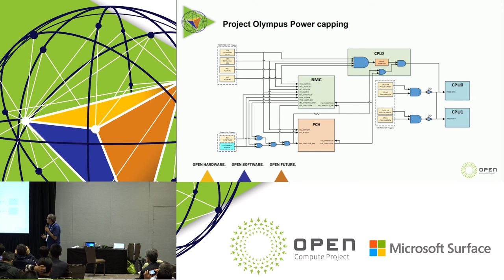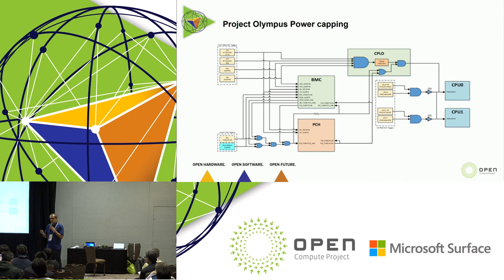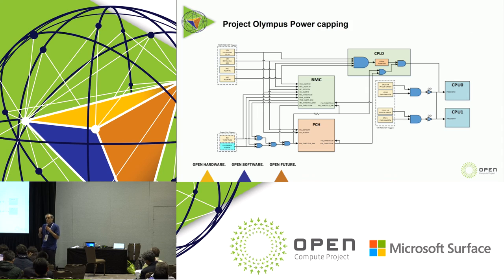The second mechanism is through the interaction between the BMC and Intel Node Manager. When we throttle the CPU, maybe we don't want to stay at the lowest frequency because of the performance impact. But we want to make sure we react to the power event quickly. So we do it through the fast proc hot first, and then the BMC sends a new policy to Intel Node Manager with the power budget defined by the rack manager or row manager at different levels. As Dave said, Intel Node Manager gradually ramps up to meet that power requirement, increasing frequency gradually to have minimum impact on the workload.